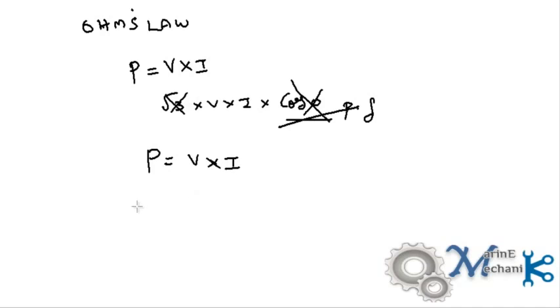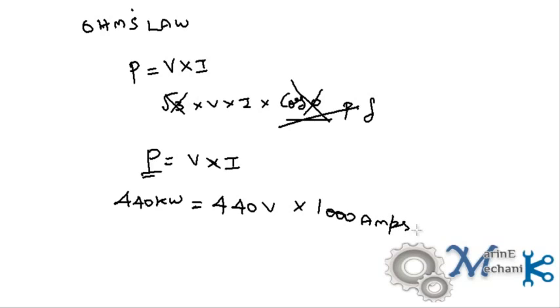Now let's understand, for a given power, let's say 440 kilowatts, if I operate the ship at 440 volts, what will the current be? It will be roughly 1000 amps, neglecting cos phi, the power factor. So to operate a ship at 440 volts, I have to design the cables and everything for 1000 amperes to achieve a load output of 440 kilowatts.